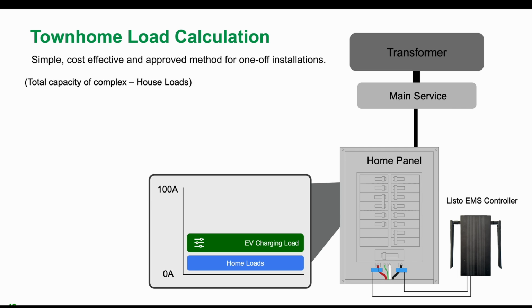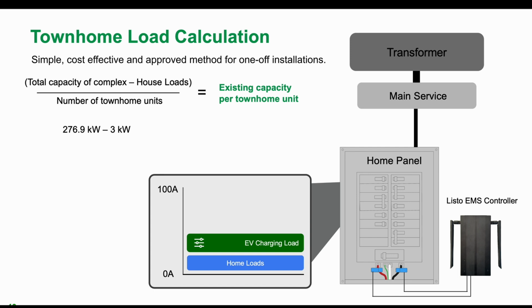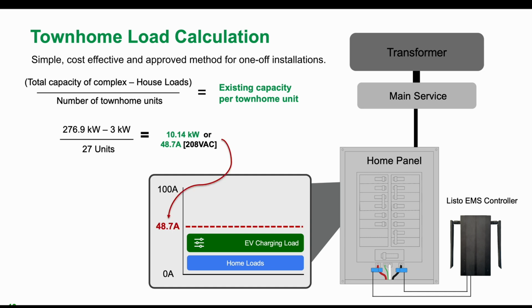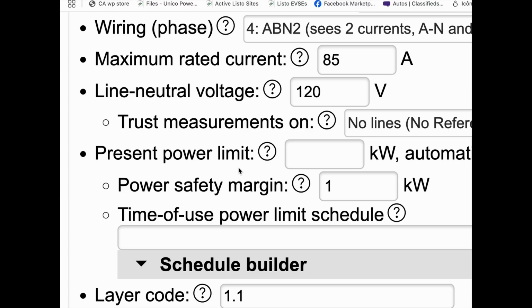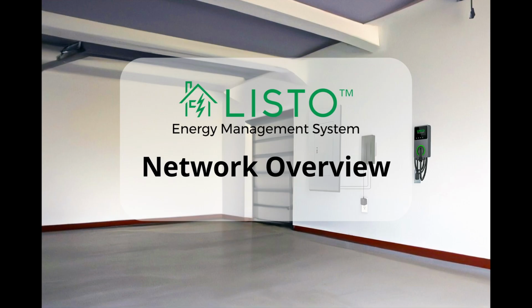Installers take the total capacity of the townhome complex minus any house loads and divide it by the number of townhome units. As the panel load approaches this limit, the EVSE output is throttled down to 0. Following the on-screen example, a 27-unit complex has a per-unit available demand of 10.14 kilowatts or 48.7 amps. Once the installer has determined the limit, they must contact Unico Power directly so this limit can be updated on the back end. Network Overview.